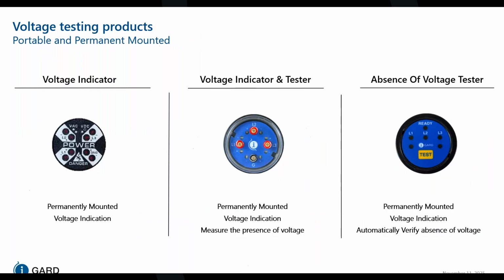There are 3 types of voltage testing devices. First one, voltage indicator. It will show if the voltage is present but cannot confirm if it is completely gone. Second is voltage indicator and tester. Adds the ability to measure voltage but still only checks for presence of voltage, not the absence confirmation. Absence of voltage tester, the safest option. It not only indicates the voltage but also automatically verifies the circuit is truly de-energized before the work begins by just pressing the test button on the module. We'll discuss this feature in the coming slides. AVTs eliminate the guesswork and provide the highest level of safety compared to simple indicators or testers and confirm the absence of voltage.